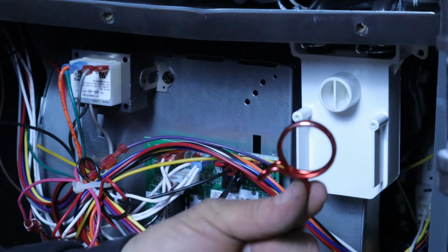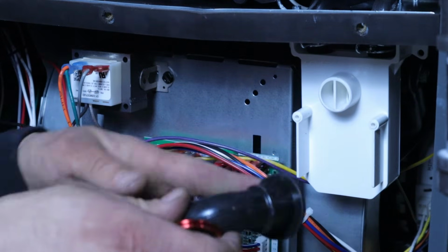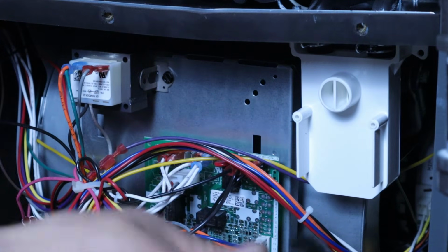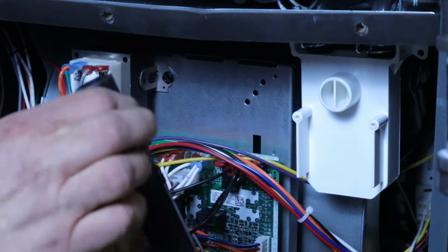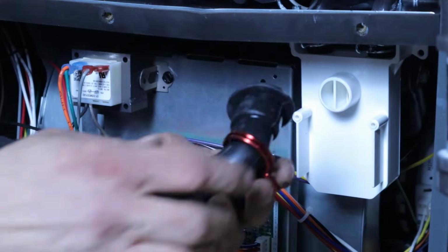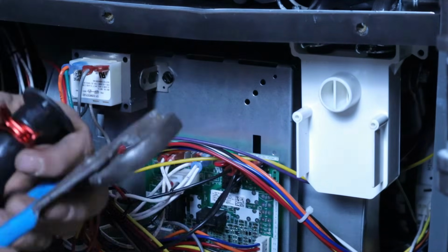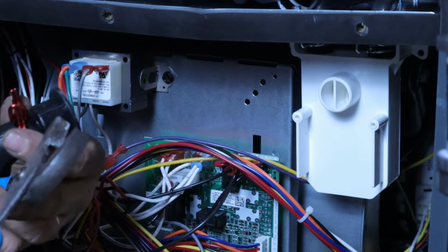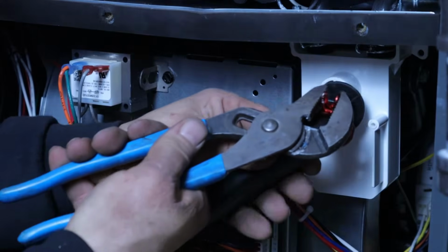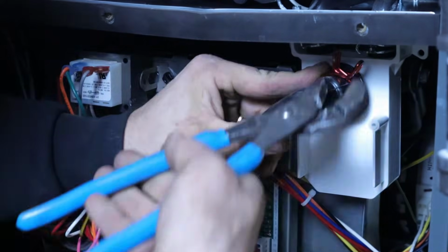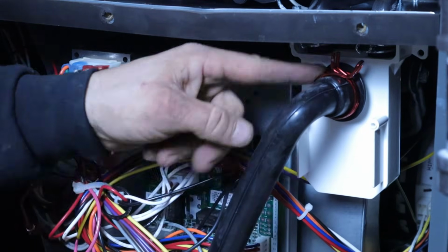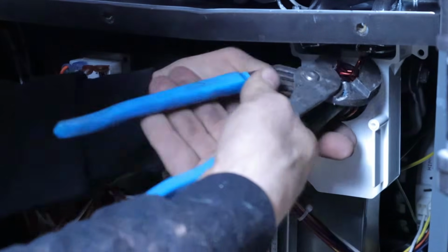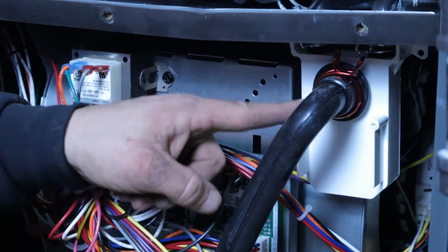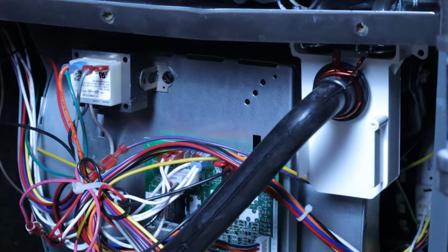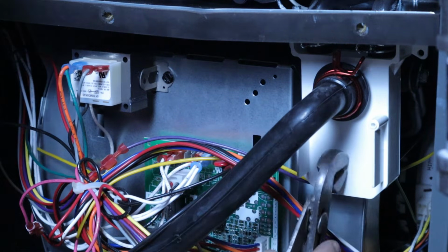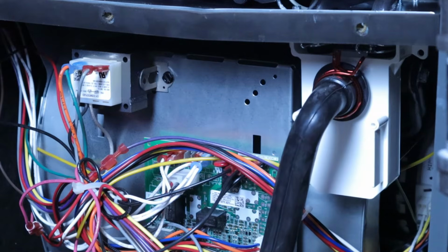So we have a large red clamp here, and we're going to be using that to clamp our hose to our trap there. So I'm just going to run it right over the top of this. I'm going to take the channel locks, I'm going to squeeze down on that clamp. I'm going to put this hose right on there. All right. And so now we're on there nice and tight. All right, and our water, once this trap fills, the water is going to overflow down this black tubing. Now we don't need to put any P-traps or anything else in here because this is already a trap. So it's just a straight run right out of the unit.